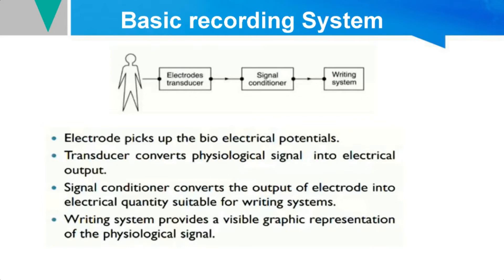This is how the recording system works. The bioamplifier acts as an intermediate between the electrodes and the display unit or output unit. The signal conditioner functions as the bioamplifier — it picks up signals from the electrode and passes the amplified signal to the display unit, which could be a pen recorder or a CRO used for telemetry purposes.